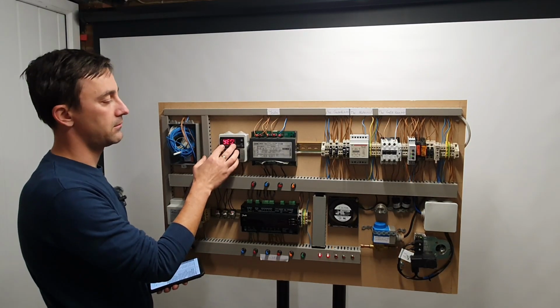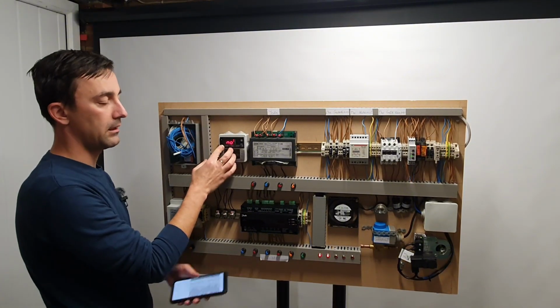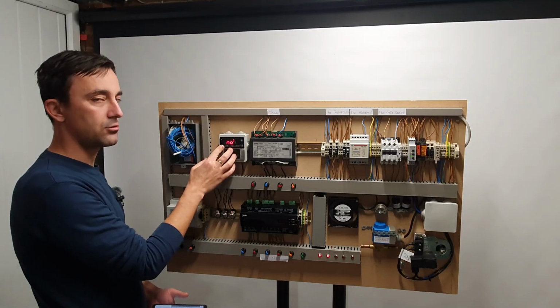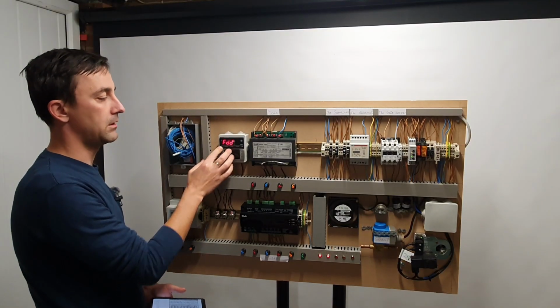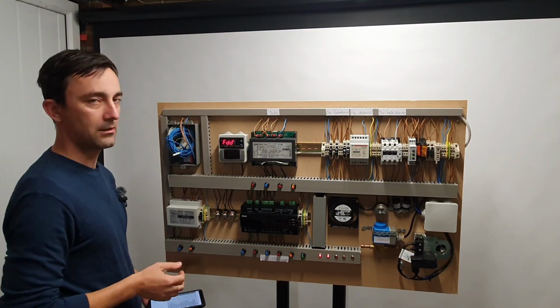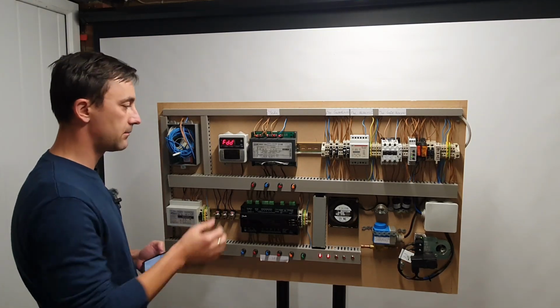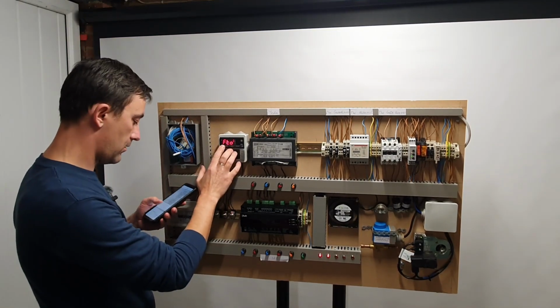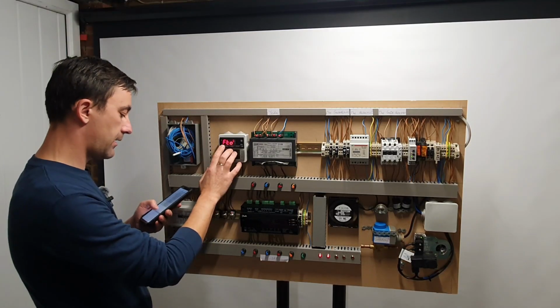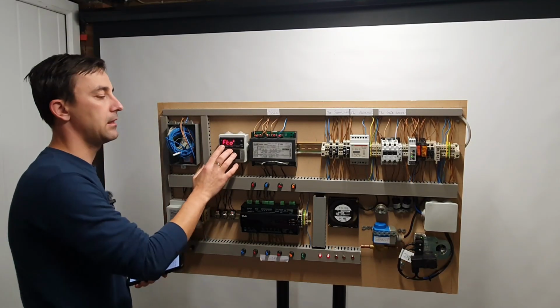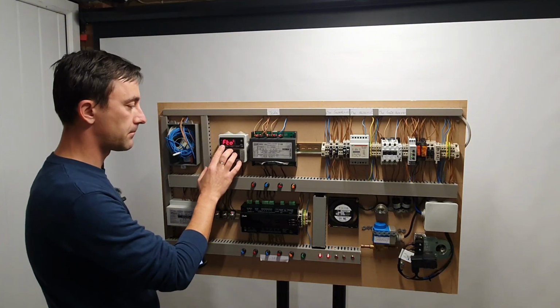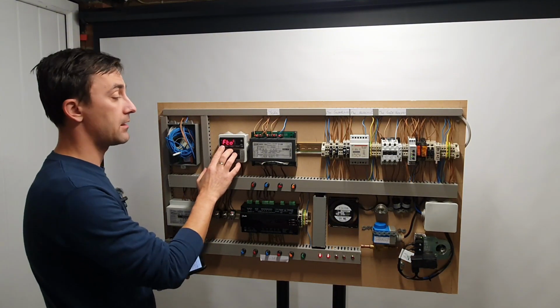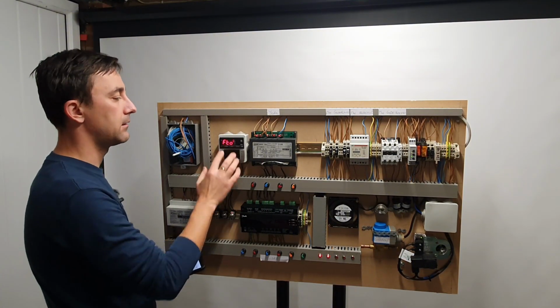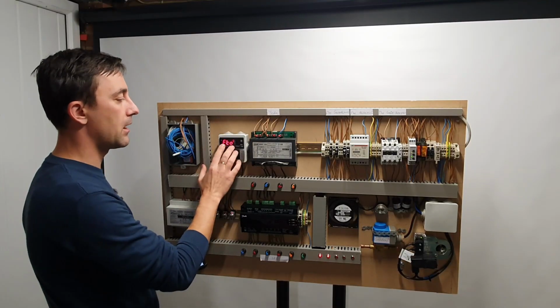FAD is fan active during defrost. 2 options, no and yes. Well, if it's an electric defrost type, then the fans should be off, because you don't want to blow the warm air into your system. FTO is evaporator fan maximum timeout. So that is when the evaporator fans will kick in. So it will be after 2 minutes.